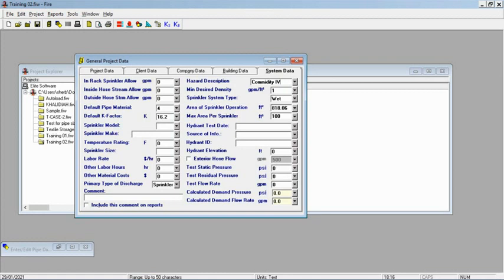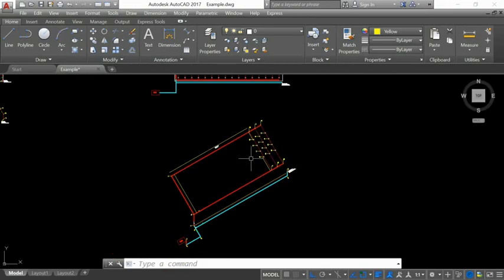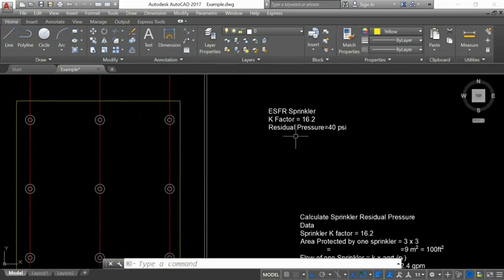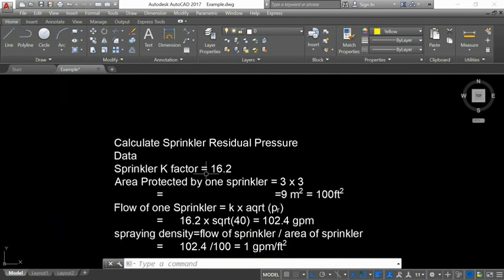Now there is another problem: the minimum desired density. How do we get the minimum desired density when the code is not directly giving it to us? The code only gives you the k-factor and the residual pressure. So we need to calculate it ourselves.